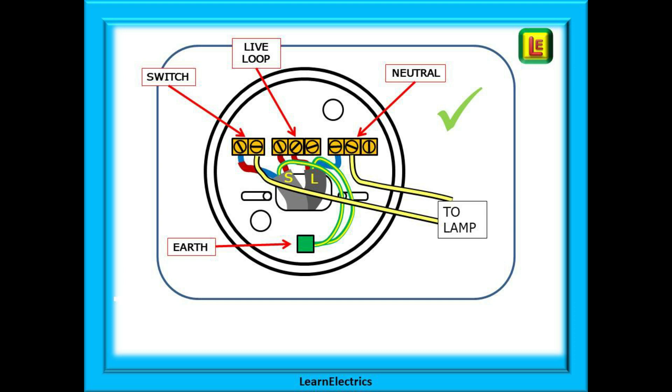Starting with the earth at the bottom and working clockwise we have the switch block, the only two hole terminal block in the fitting. In the middle is a three hole live loop block. This block is permanently live and then the three hole neutral block on the right. Notice the two cables entering the rose in the center. The live cable from the consumer unit or previous room marked here as L and the switch cable that goes to and returns from the room switches marked S and lastly the two wires that go to the lamp or bulb.